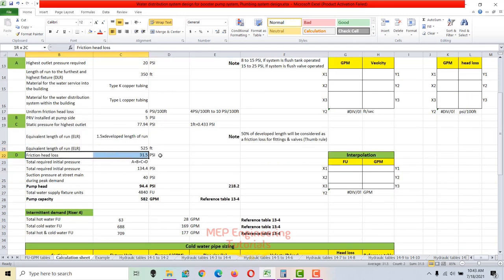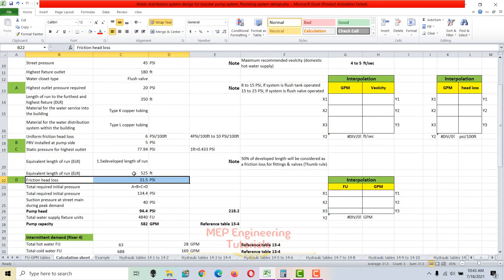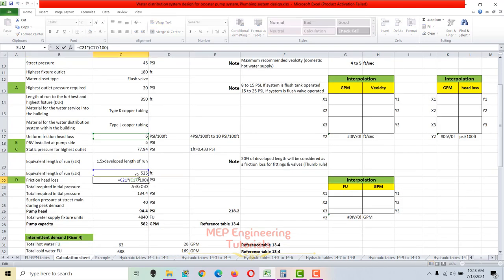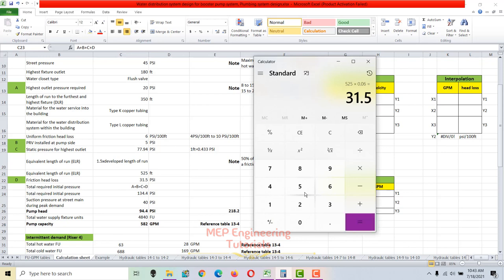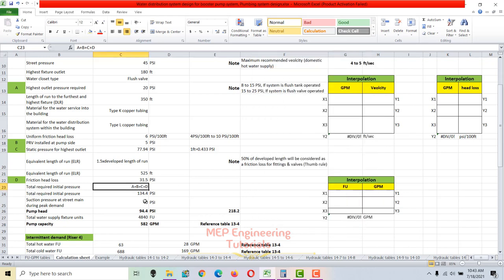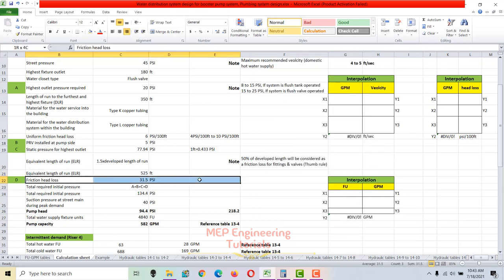The friction head loss is calculated by multiplying the equivalent length of run by the uniform friction head loss. With a uniform friction head loss of 6 psi per 100 feet (0.06) and an equivalent length of 525 feet: 525 × 0.06 = 31.5 psi friction head loss. This accounts for straight pipe, fittings, and valves.